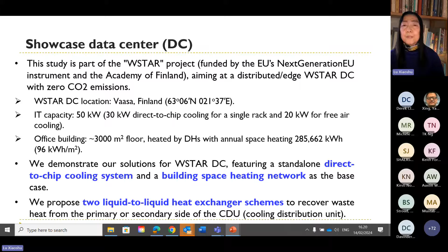I demonstrate our solution for W-Star data center using 4 cases. The first is a direct-to-chip cooling system without heat recovery, and the second is a building space heating network without heat recovery. These 2 cases serve as base cases. Now I propose 2 liquid-to-liquid heat exchanger schemes to recover waste heat from the primary or secondary side of the CDU. Then I compare the performances.